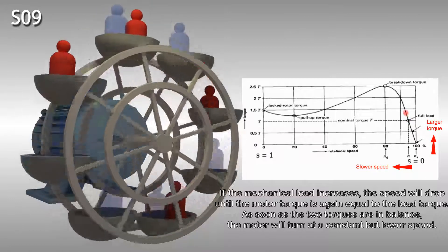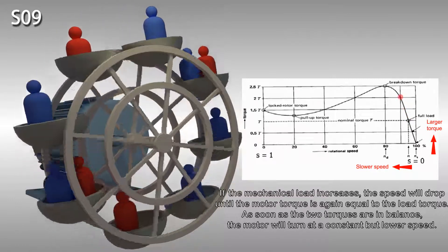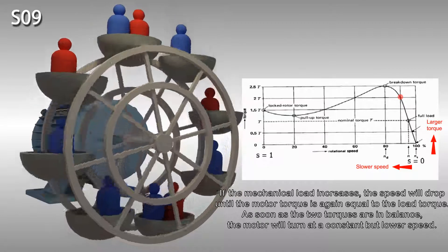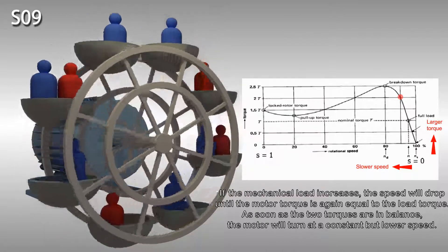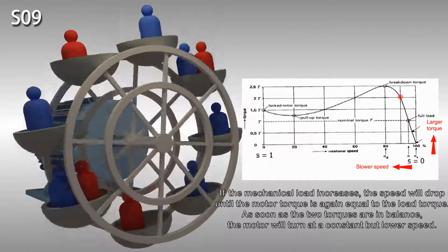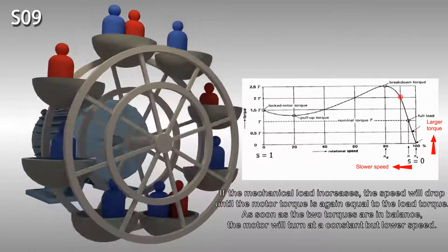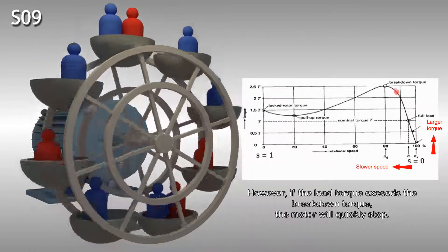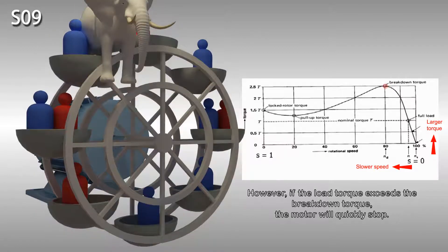If the mechanical load increases, the speed will drop until the motor torque is again equal to the load torque. As soon as the two torques are in balance, the motor will turn at a constant but lower speed. However, if the load torque exceeds the breakdown torque, the motor will quickly stop.